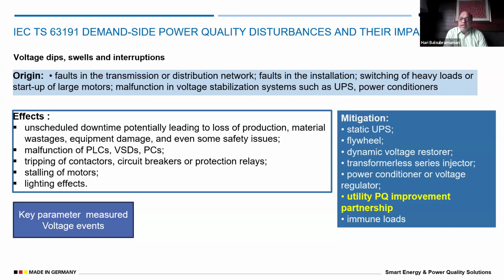Mitigation can be with static UPSs, flywheel arrangements, dynamic voltage restorers, power conditioners, or a utility PQ improvement partnership. I marked it in yellow to make it important. None of us today shares with the utility what kind of problems we have. One reason is that we don't have the data, which is different. But even if we have data, we don't share it with the utility to say, look, I have experienced these kinds of power quality problems. So many times the voltage has dropped. We need to share this with the utility. That's when they will also know.